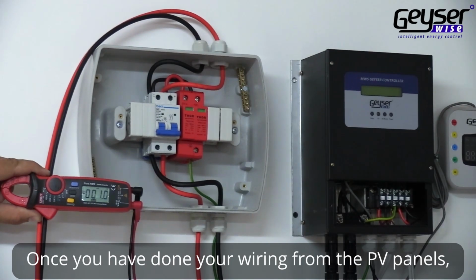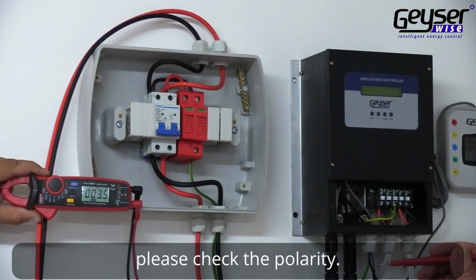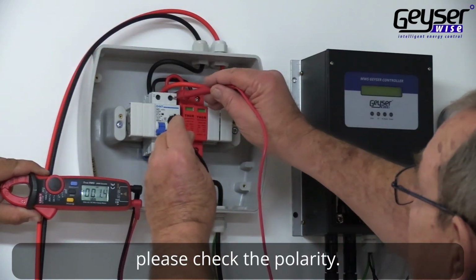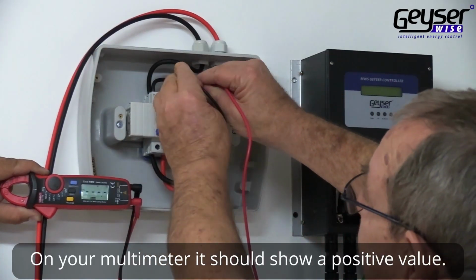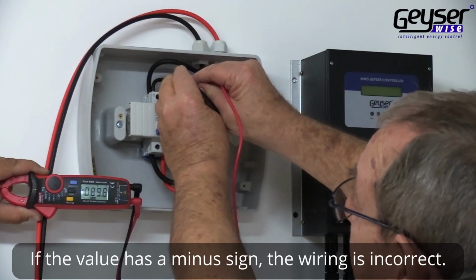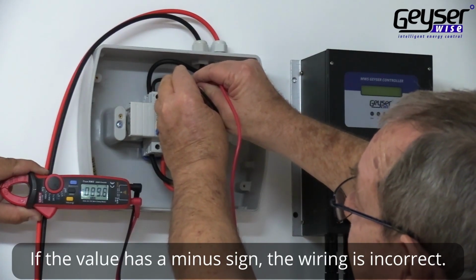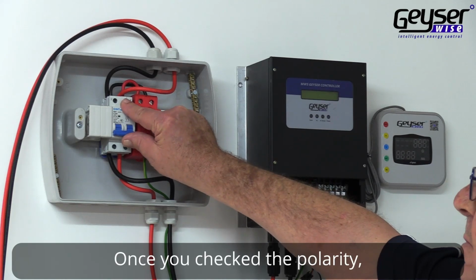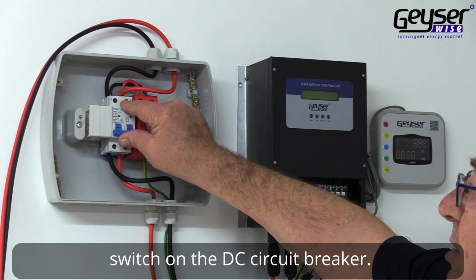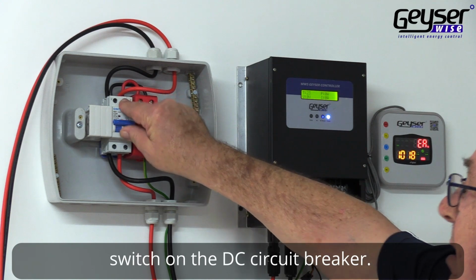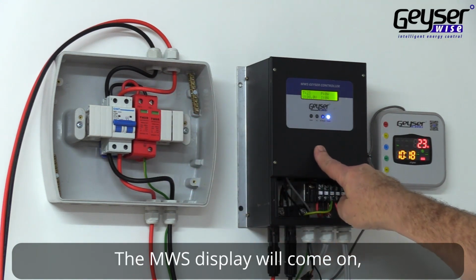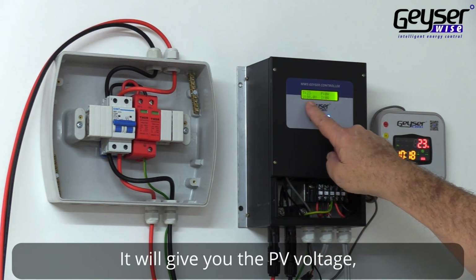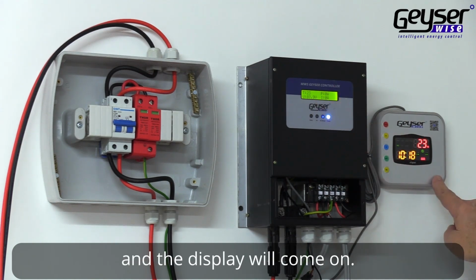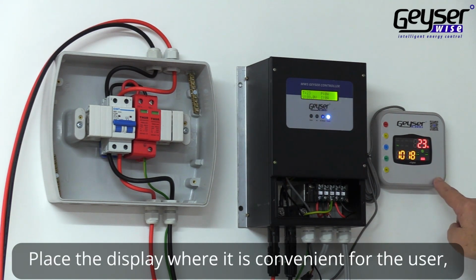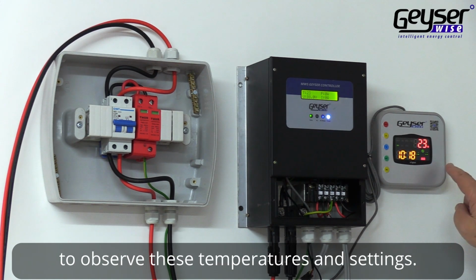Once the wiring from the PV panels has been done, please check the polarity. The reading on your multimeter should be positive. If a negative value is shown, the wiring has been done incorrectly. Once the polarity has been checked, switch on the DC circuit breaker. The MWS display will switch on, showing you the PV voltage. The display will also switch on. The display should be placed where it is most convenient for the user to check the temperatures and settings.